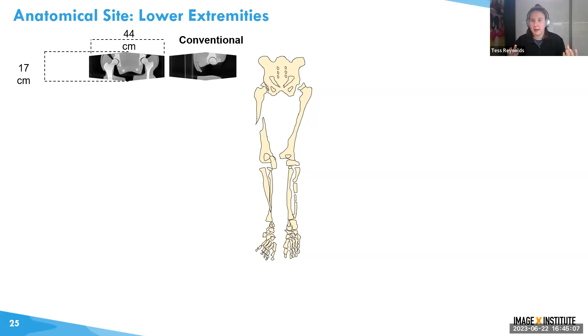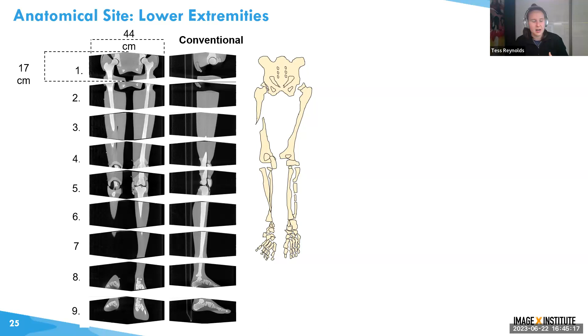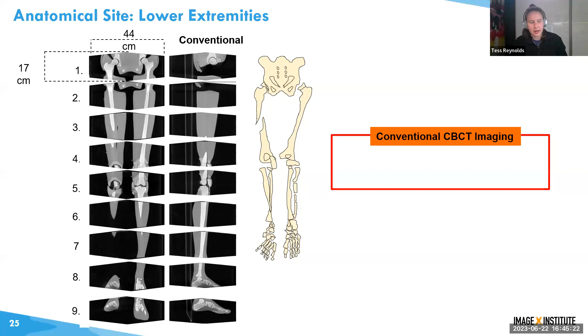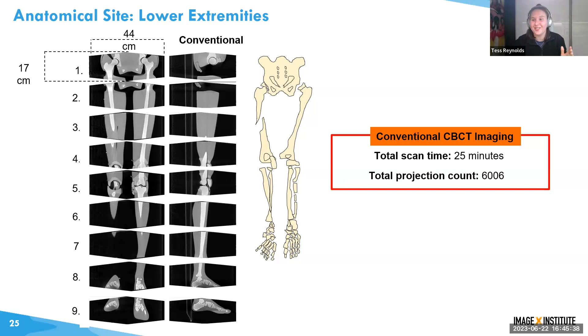If we take a conventional scan, as I said, we're potentially able to just capture the whole hips, but we need that entire length. So if we go down, in this case, we'd need 9 conventional scans to get the whole piece of anatomy in, and this is going to add up pretty quickly. To actually do this on a conventional system is going to take 25 minutes, which is way too long for any type of imaging, especially in the interventional room. No one is going to stop for 25 minutes to do this. And you have an extremely high projection count, so that's a lot of dose to the patient.